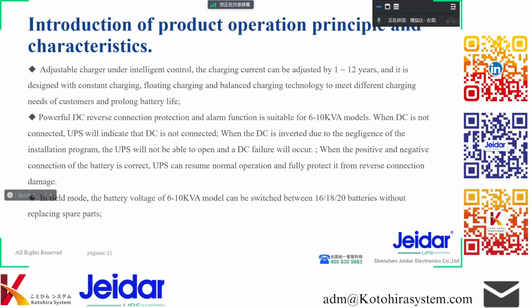Powerful DC reverse connection protection and alarm function is suitable for 6 to 10 kVA models. When DC is not connected, UPS will indicate that DC is not connected. When the DC is inverted due to the negligence of the installation program, the UPS will not be able to open and a DC failure will occur. When the positive and negative connection of battery is correct, UPS can resume normal operation and fully protect it from reverse connection damage.